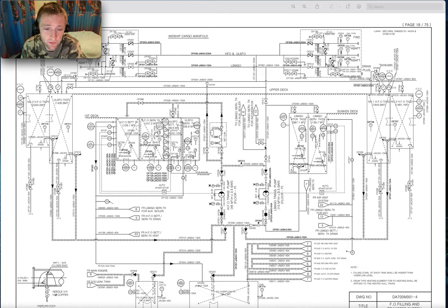We do not have any start and stop when we are giving outside here to the manifold, so we need to control the level on the tanks, and from the tanks we are suctioning, we need to control them. And also, as you can see here, if we suction from an overflow tank, we also need to be there and control the pump locally, so the pump will not stop if you are suctioning from an overflow tank, or from a fuel oil clean leak tank, as we have here.